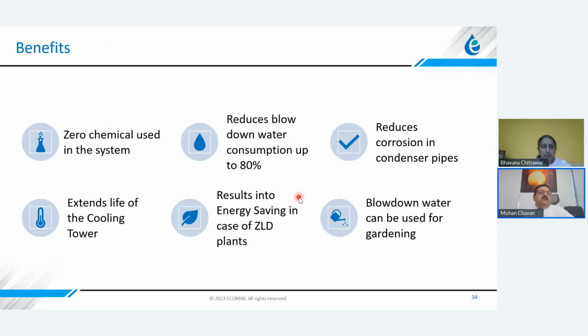Let's look at the benefits that electrolysis-based technologies offer. Of course, it's a zero chemical technology. It reduces blowdown water consumption by up to 80%. It will reduce the corrosion in the condenser pipes. It extends the life of the cooling tower, which means your frequency of changing fills will reduce.